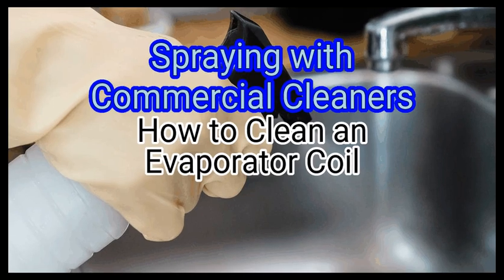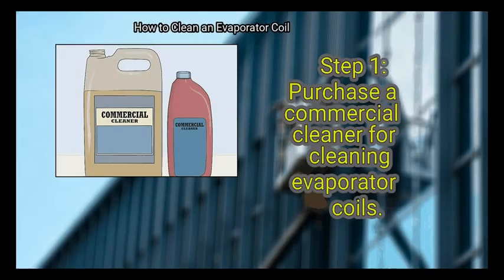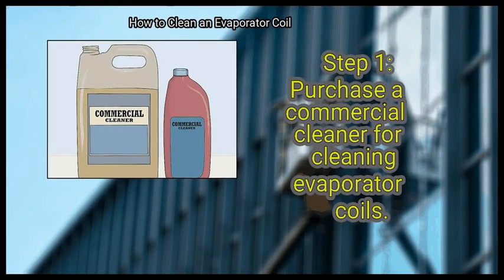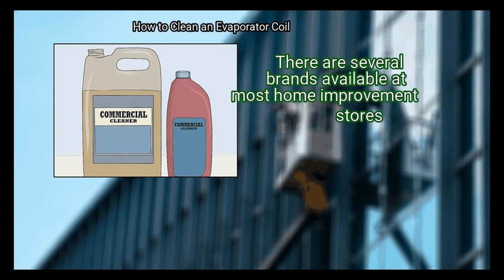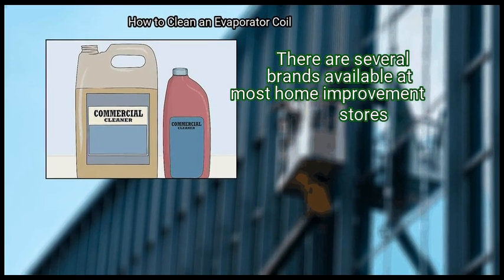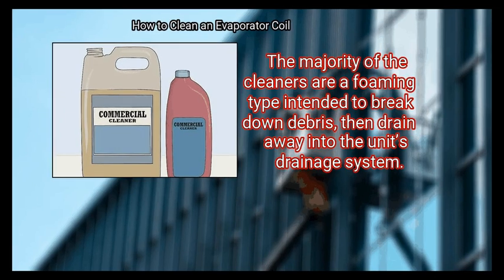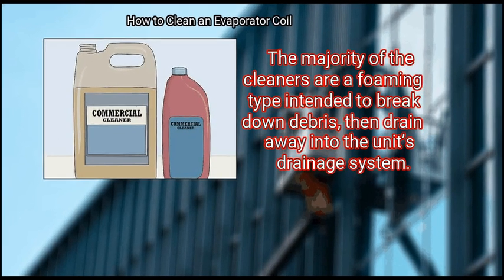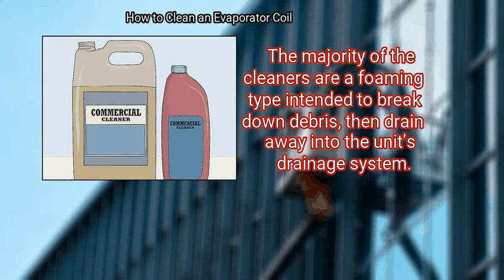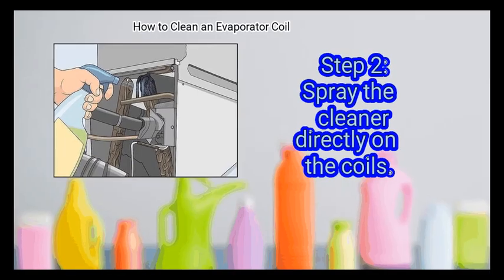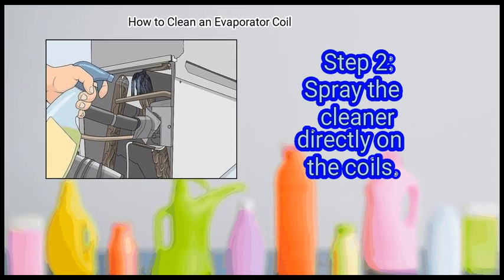Method 4. Spraying with commercial cleaners. First, purchase a commercial cleaner for cleaning evaporator coils. There are several brands available at most home improvement stores. The majority of the cleaners are a foaming type intended to break down debris, then drain away into the unit's drainage system. Step 2. Spray the cleaner directly on the coils.